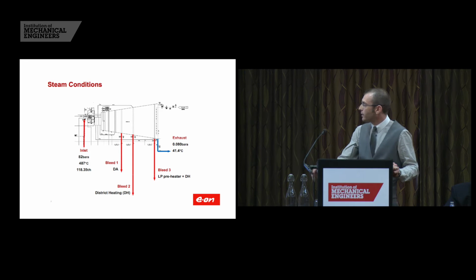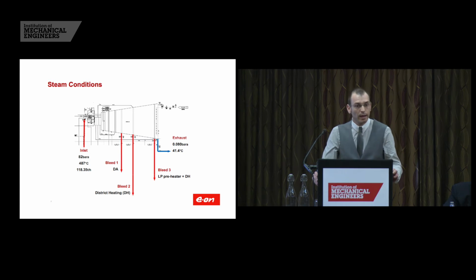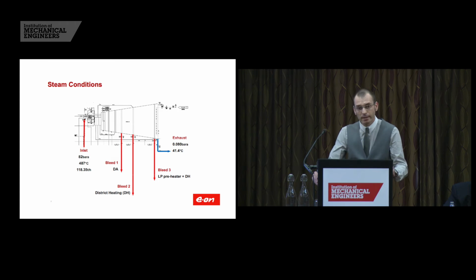A little bit about the steam conditions for the steam turbine. We have 82 bar 487 inlet pressure. As I've mentioned before, we have 3 uncontrolled extractions. Bleed number 1 goes to the deaerator, bleed number 2 to the district heating building, and bleed number 3 to district heating and the LP preheater.